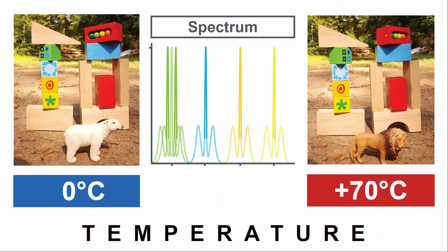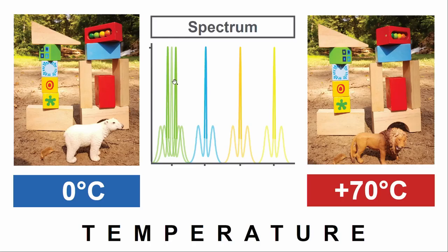One example for a test could be, let's take the temperature, and there are actually, let's say, two different ways to test. One would be, we just cool it down, the transceiver, to 0 degrees centigrade, measure the optical performance. If we are bit error-free, great, check. We're gonna heat it up to 70 degrees. It's fine. You might see during this testing stage that one wavelength is going to drift away a little bit. Like this one here, the spectrum of the green wavelength is going to drift away a little bit, but at some stage it's going to be normalized again. This would be one test case.